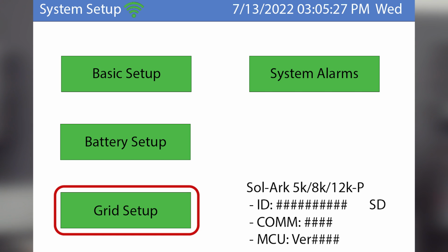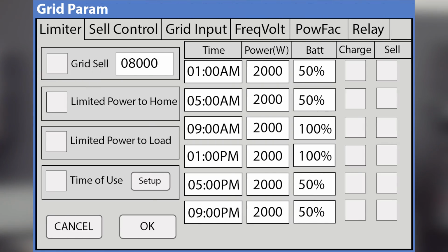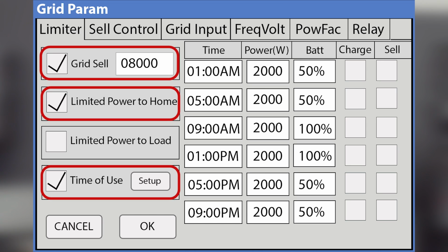Next up is the grid setup tab. In the first tab, called limiter, this is where you pick the mode of the inverter. If you want the inverter to sell to the grid only, you'd pick grid sell. If you'd like it to discharge the battery and offset your home bill during the day, you do time of use. You can get pretty fancy with these settings because you can have several different modes on at the same time to get different functionality. One of the more complicated, and also the most popular way this is set up, is to have grid sell, limited to home, and time of use all on at the same time.